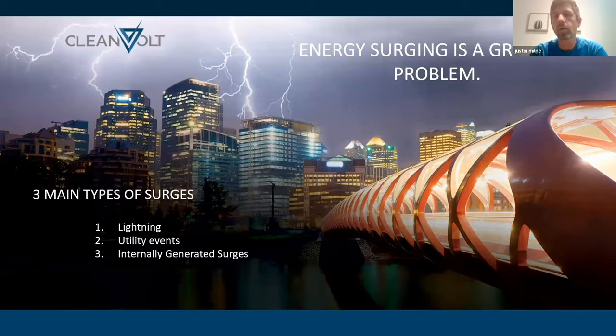So the difference between the three is that the first two occurrences are a high rise in voltage that are caused by either a lightning strike or some sort of mishap with weather or accidents on the utility grid. And of course, the third one is more based on energy surges that are created by voltage drops when your equipment turns on, or when your electronics are doing their normal thing due to their switching power supply. They generate a lot of harmonics, and of course that deviates the voltage waveform and creates energy surges. So we're going to go over an example of each one of these items. The first video here is of a lightning strike.